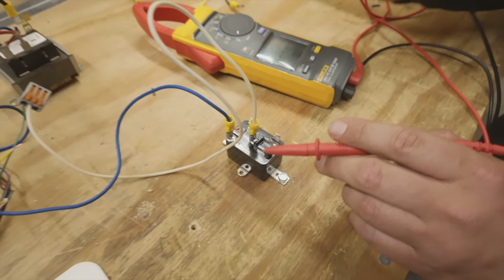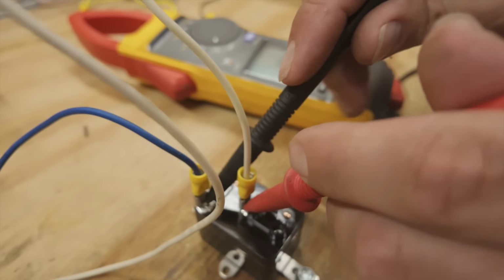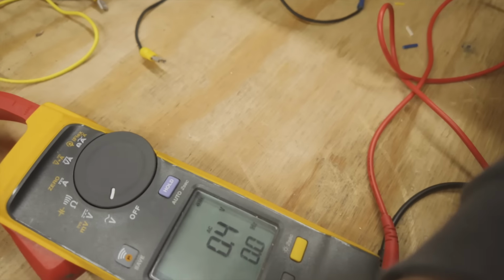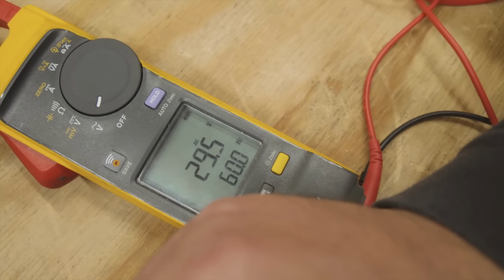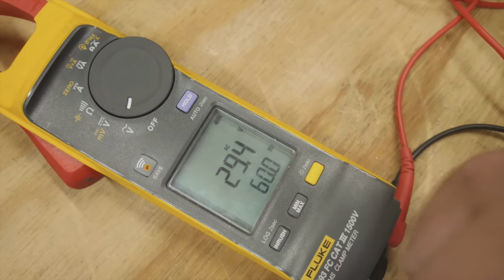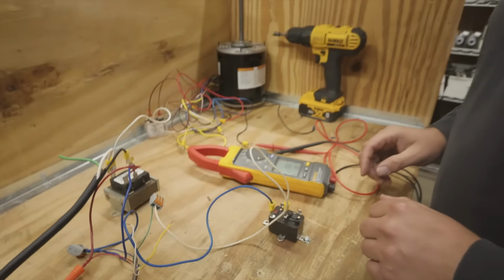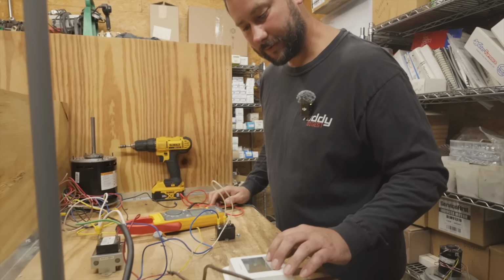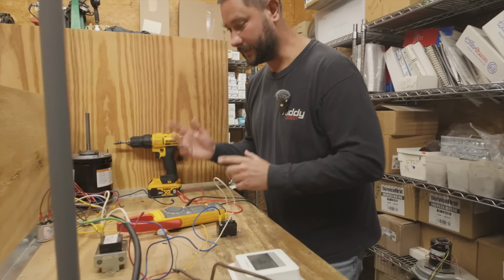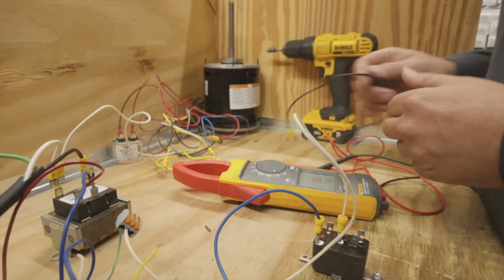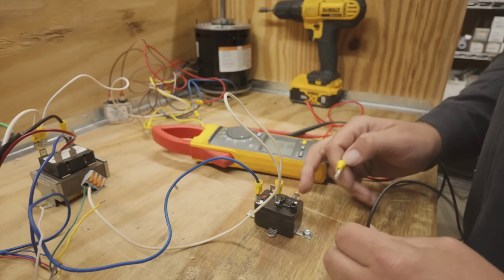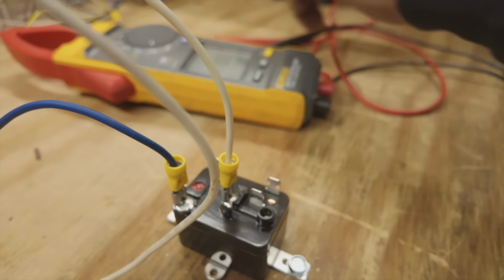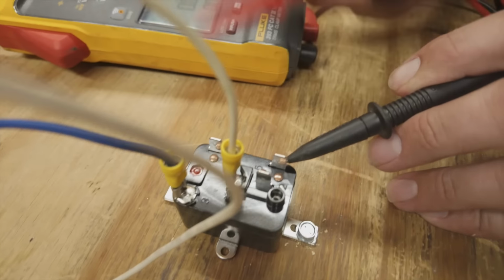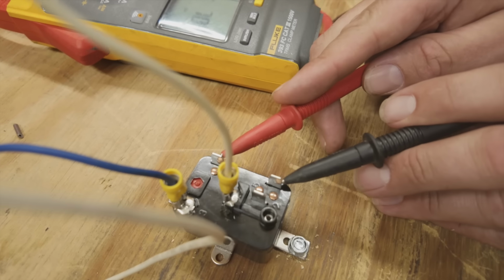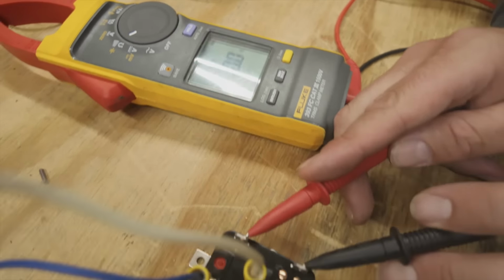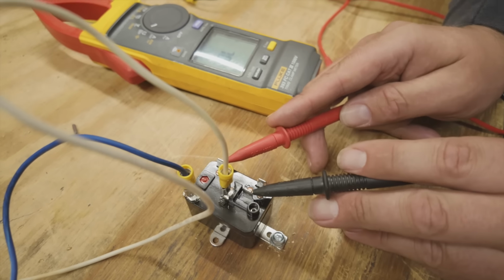Now let's go back to volts, and let's measure between 1 and 3. Why did it close? Why did it open? Because, well, we received voltage. 29 volts. Now, let's go ahead and turn this back off. We'll hear a click, and let's connect our wires for our fan motor. So this was normally, let's see, which one do we want to connect? Go back to continuity. This is already normally closed. So if we connect our fan motor here, it's going to kick on. We're going to go between 4 and 2.